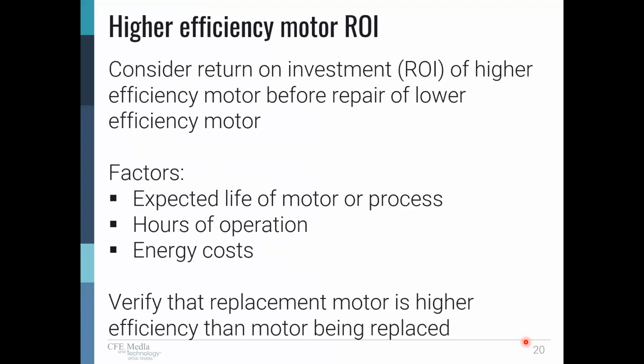But what if we have a motor with the same 10-year period, but it's going to run 8 hours a day, roughly 2,000 hours a year? Now we have 2,000 times 10, 20,000 hours against 90,000. So for the same energy costs, the motor that's going to run longer is going to cost 4.5 times more, 90 divided by 20. So for the one that's running the longer period, we're much more concerned about our return on investment because of what we're going to get paid back. Also, because we're going to get so much payback, it makes that evaluation process easier in terms of thinking about things like maybe we do want to replace an older motor with a premium efficient motor.